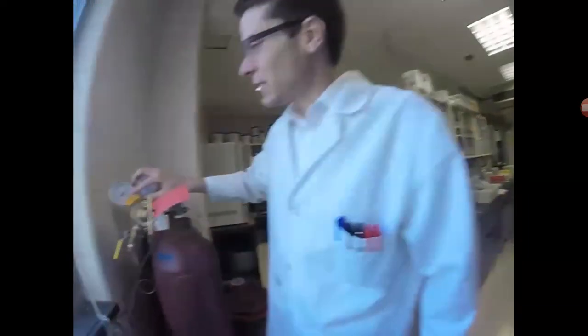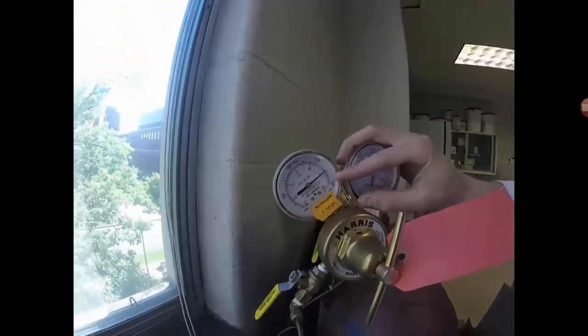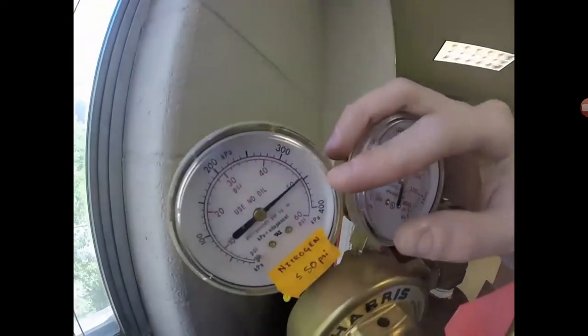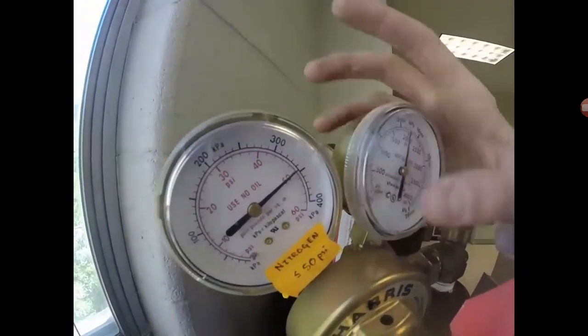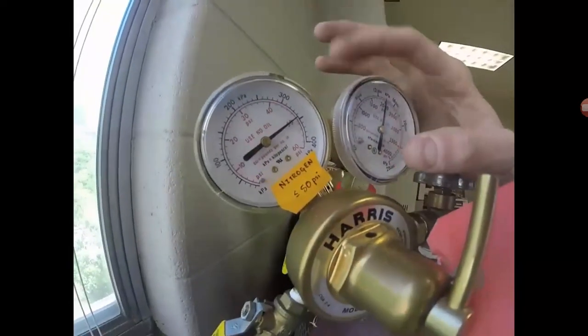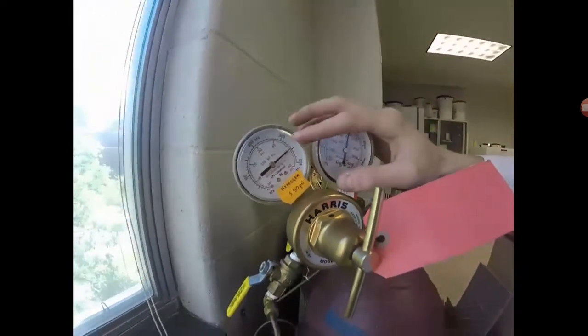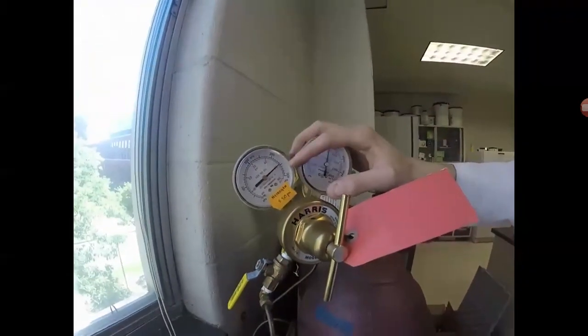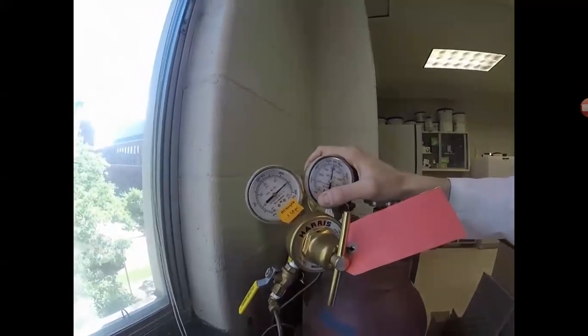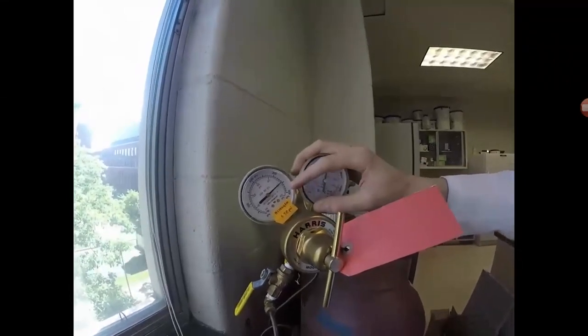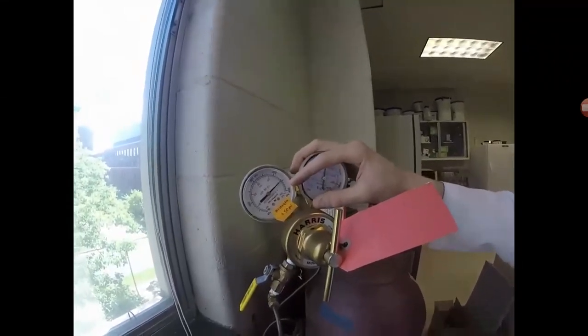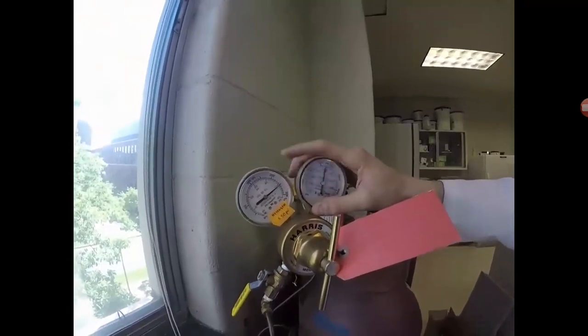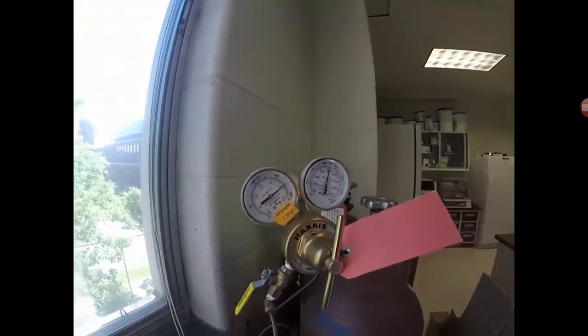You can look at this one. I mentioned that the pressure was a little above 50 before, so now the gas is actually flowing. The pressure is exactly 50, so you can just maintain it at that. This is also a good way to see which gas is flowing. You can watch the gauge change. If you keep watching, it should jump here just a little bit. So the pressure is a little bit higher now. That just indicates which one's going.